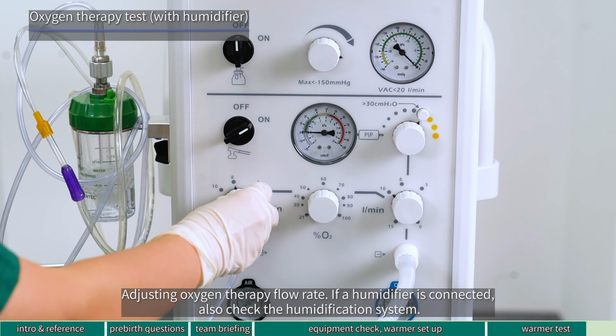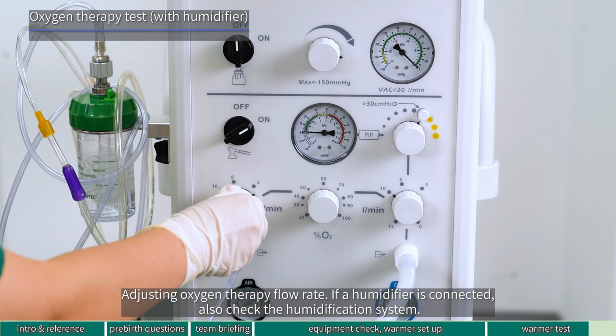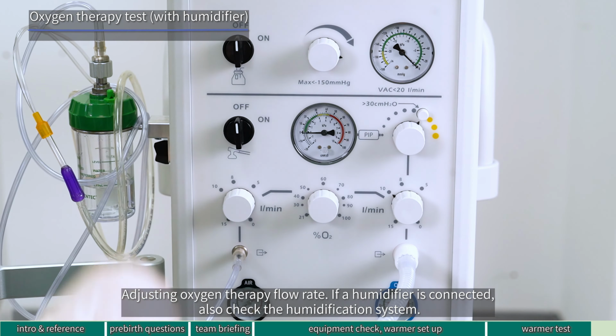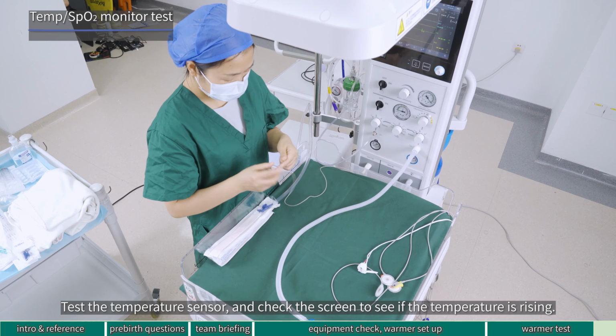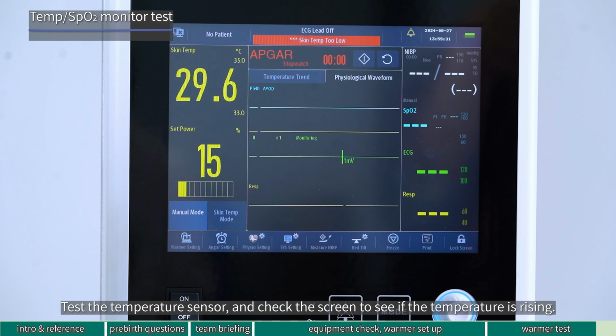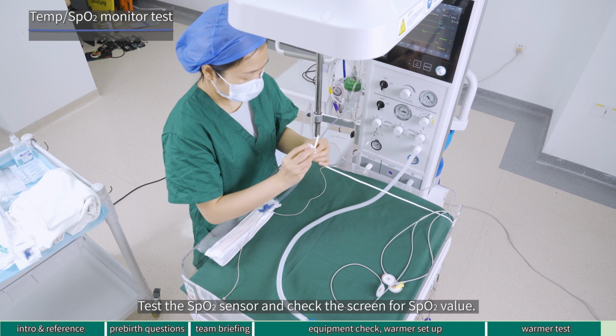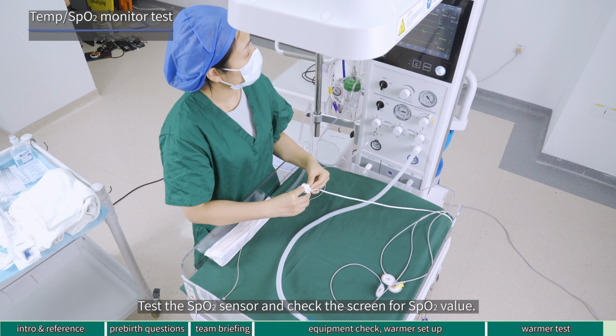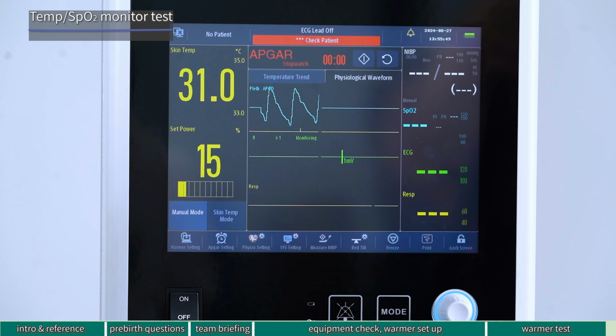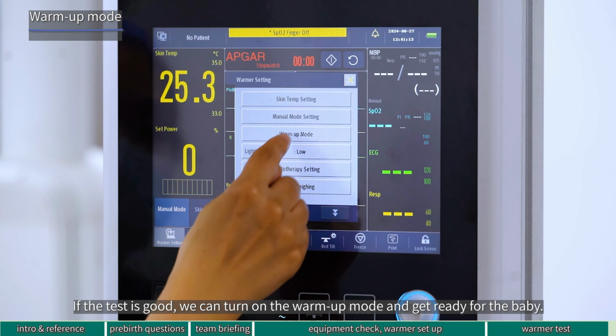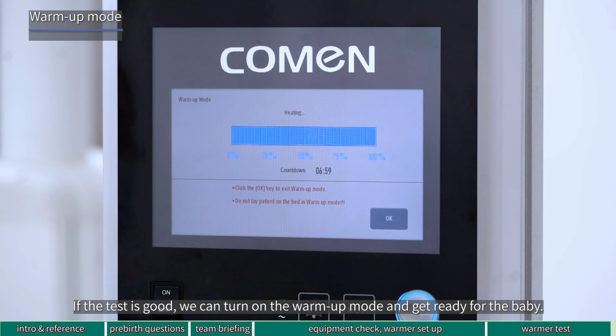Adjusting oxygen therapy flow rate. If a humidifier is connected, also check the humidification system. Test the temperature sensor and check the screen to see if the temperature is rising. Test the SpO2 sensor and check the screen for SpO2 value. If the test is good, we can turn on the warm-up mode and get ready for the baby.